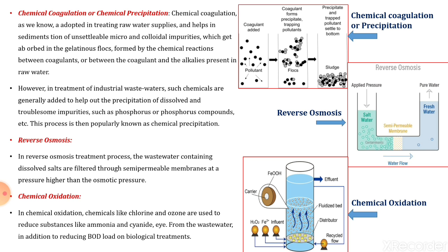In chemical coagulation or precipitation, suspended solids which are not readily settleable have chemicals added to initiate flocculation. Due to the addition of chemicals, floc formation occurs, and since this floc is heavier than water it starts settling at the bottom. The supernatant water is taken from the top and sludge is removed readily. This is called chemical coagulation or precipitation.